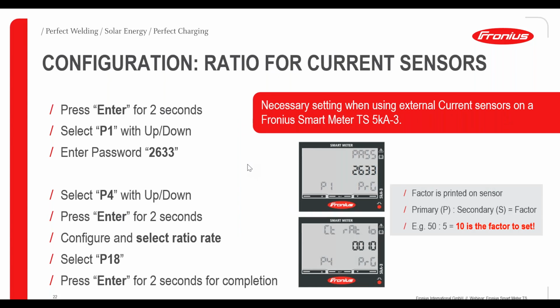Another important thing to keep in mind is, if you are using the commercial smart meter, the smart meter 5 kiloamps, you also need to configure the ratio for the current transformers, because there are lots of different current transformers available on the market with different ratios, so you need to set the correct ratio. The current sensor factor from primary to secondary, for example from 50 amps to a secondary of 5 amps, gives a factor of 10, which needs to be set within the display of the smart meter. Of course, it is always different depending on your choice of current transformers, but normally the factor is printed on the side of the current transformers.